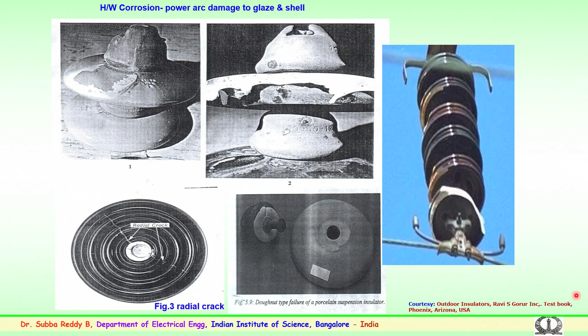And apart from this, there are natural conditions which we discussed. These are again the man-made conditions, because of the growth of industrialization, where because of the burning of agriculture waste, you see the ash settling on the insulator surface over a period of time, and interacting with dew and fog, insulator flashover does happen. Similarly, EHV or UHV lines which pass near industries: a lot of smoke from the industries, big kilns, cement industries or chemical industries, these pollutants or contaminants settle on the insulators over a period of time, become brittle, then become conducting because of monsoon conditions or because of fog and dew, the layer which is formed there conducts and the flashover happens.